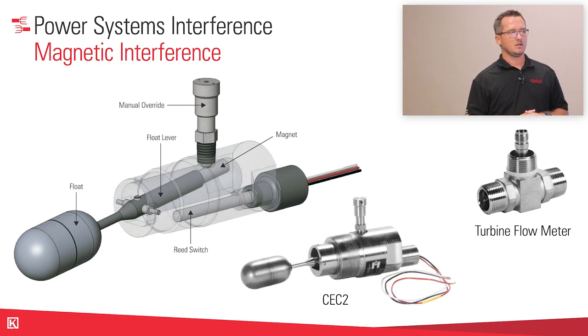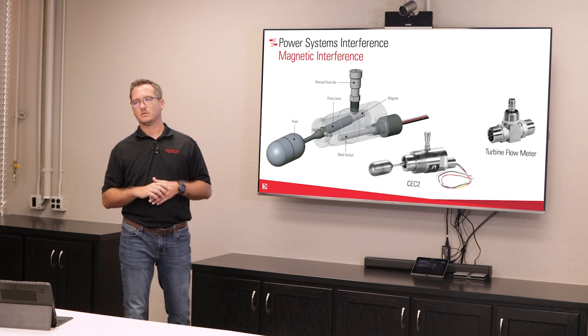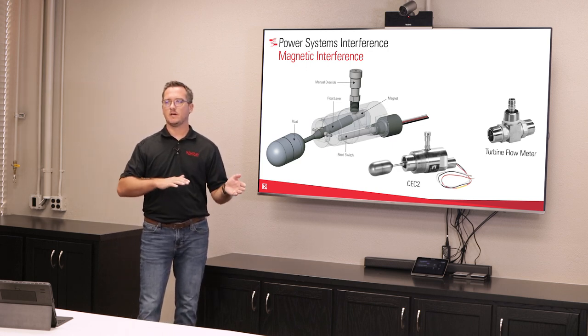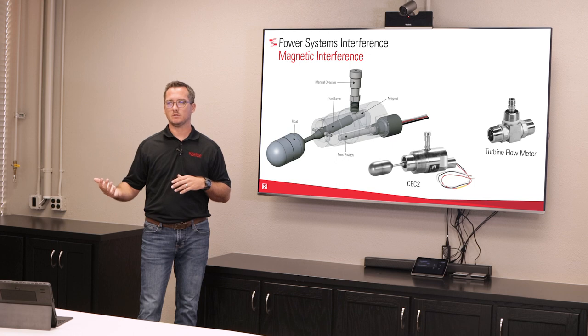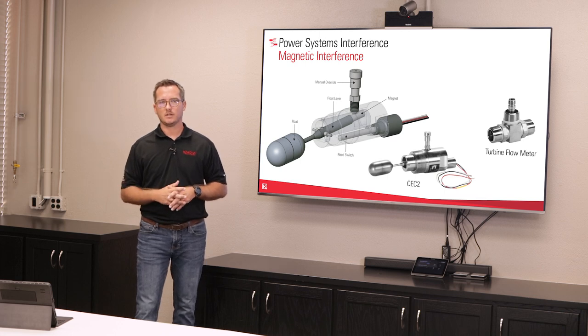One issue that we've dealt with before is on a compressor skid, you've got a metal skid without a bonding cable, and you've got high pressure liquids going through a metal system. It creates a magnetic field around it, and it'll cause your float to tell a different level than it really is. So it can cause a lot of issues out in the field for you.